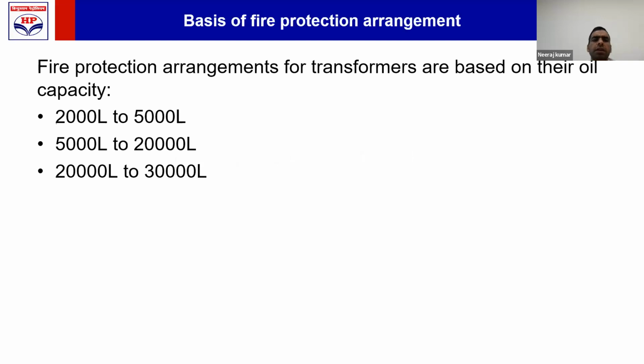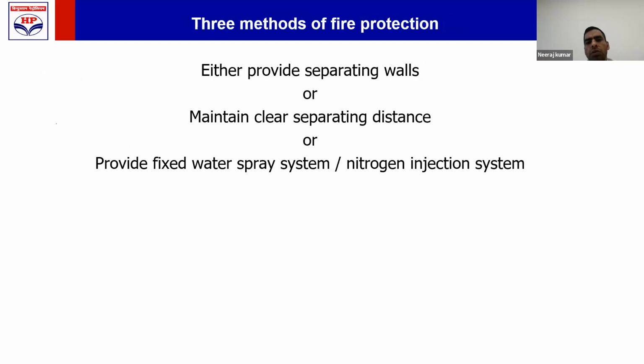the firefighting arrangement, fire protection arrangement will be based on the oil capacity of transformer. The oil capacity of the transformer is divided into three parts: up to 5,000 liter, up to 20,000 liter, up to 30,000 liter. 5,000, 20,000, 30,000. What we need to do for transformers will depend upon what is the oil capacity of transformer.